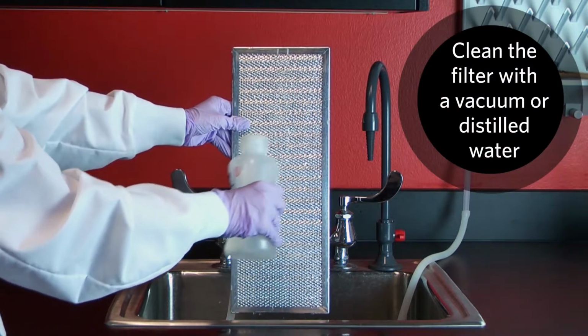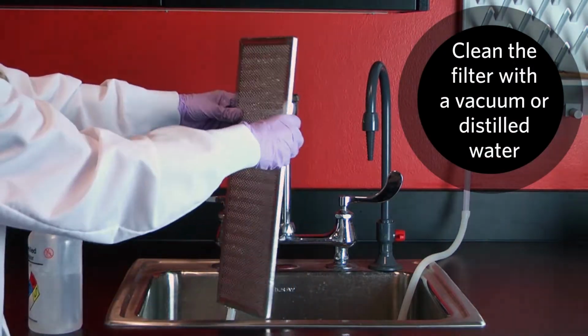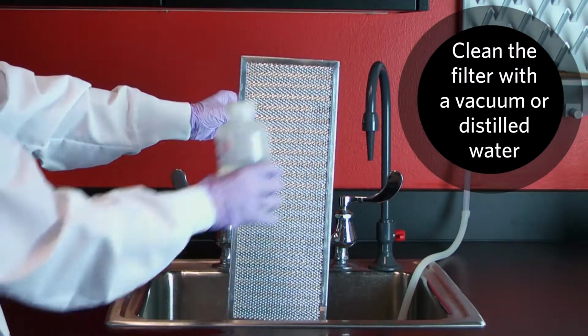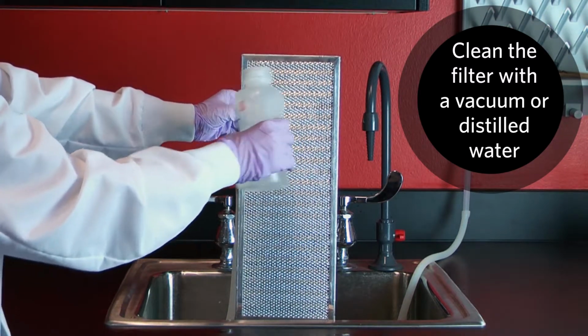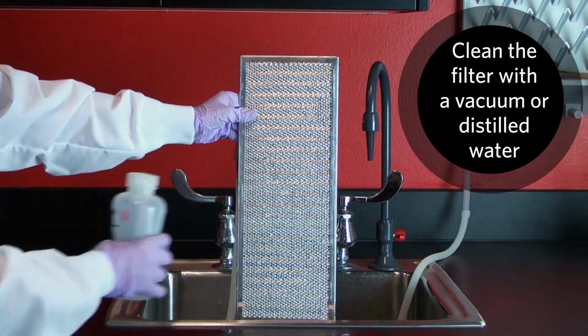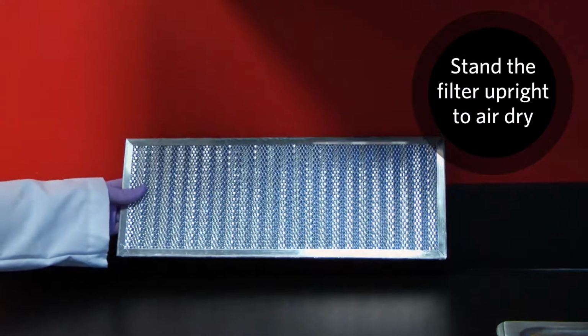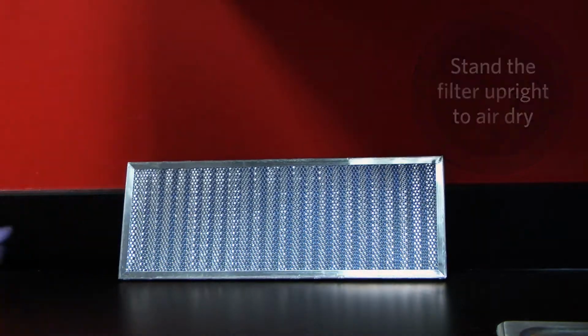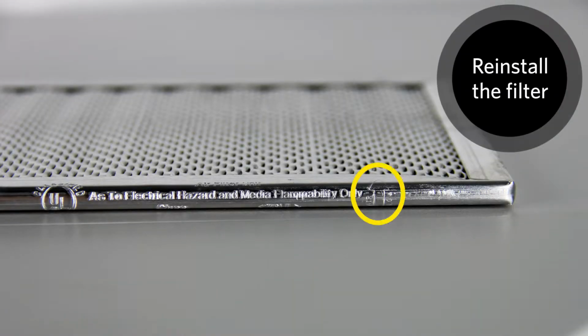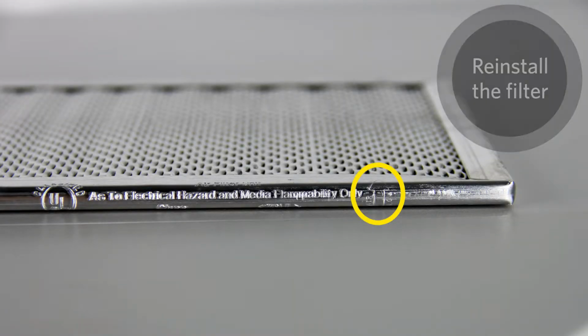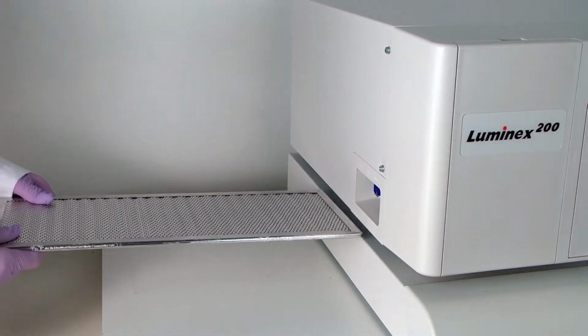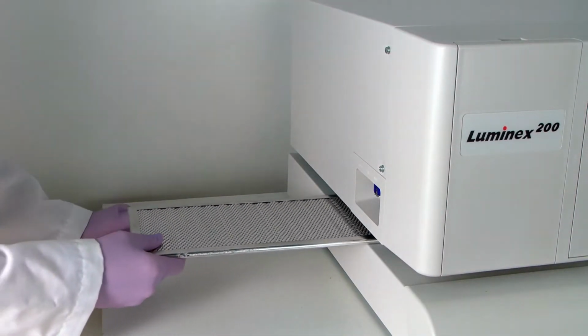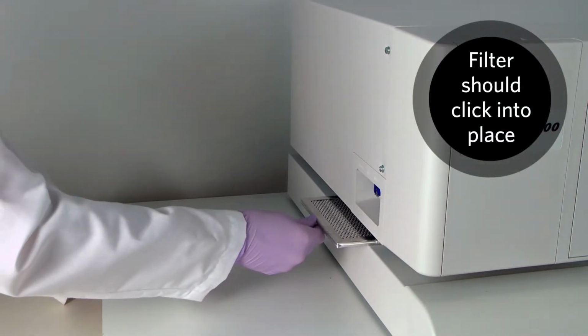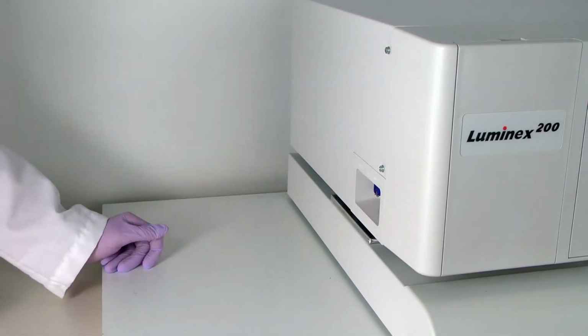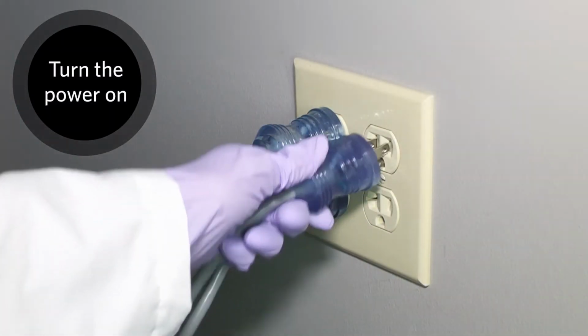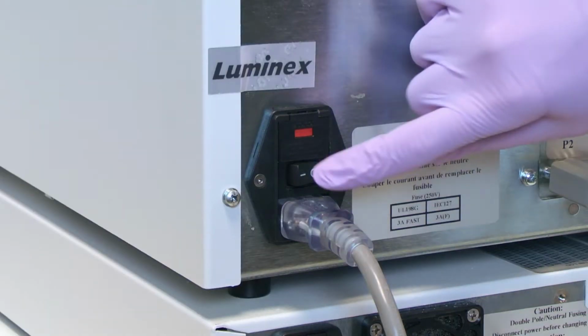Clean the filter with a vacuum or with distilled water. Stand it upright to air dry. Reinstall it with the arrows facing up. The filter should click into place. Plug in and turn on the Luminex 200 analyzer.